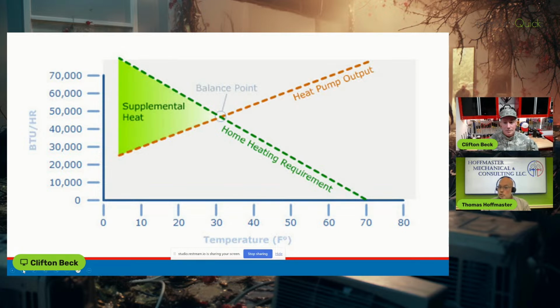However, that doesn't always tell the full story. The story gets larger and more involved, because that economic balance point just tells us at what point we need help, if you will, but it doesn't mean customers will be comfortable at that temperature. As the temperature declines and the capacity of the heat pump declines, as we get closer to that balance point we may find they start to lose comfort. Because as the output temperature of the heat pump goes down, a lot of the surfaces in the area outside the envelope of the house that radiate temperature start to fall too, so the mean radiant temperature declines and we start having comfort issues.